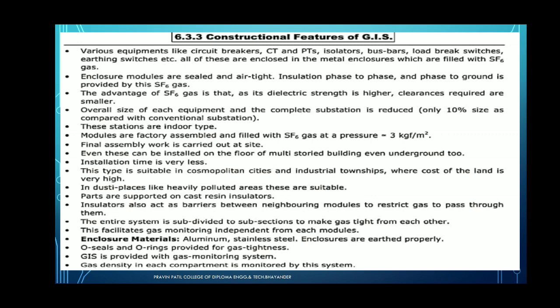Now we have to see the construction features of the SF6 or gas insulated substation. The various equipment like the circuit breaker, current transformer, potential transformer, isolator, bus bar, load break switches, earthing switches, etc. All of these are enclosed in the metal enclosures which are filled with the SF6 gas. This is the main construction feature of the gas insulated substation. Means these all equipments are enclosed in the metal enclosure and filled with the SF6 gas.